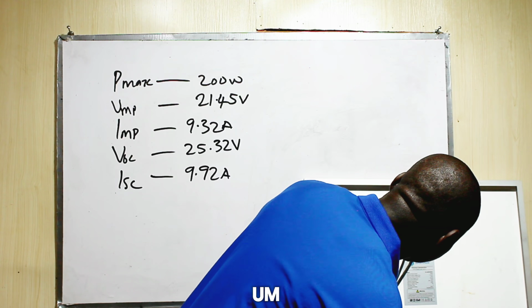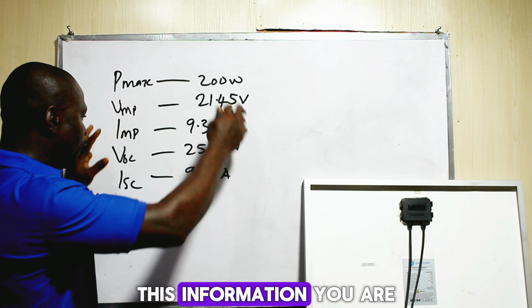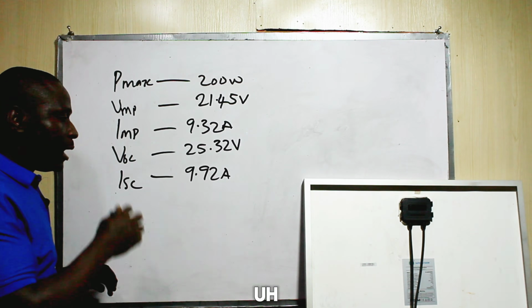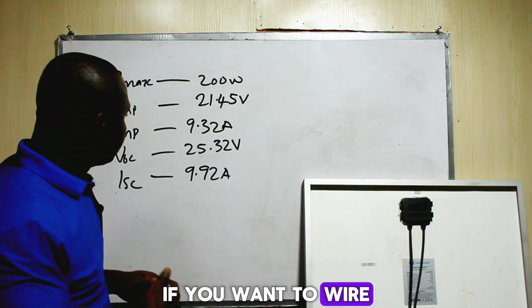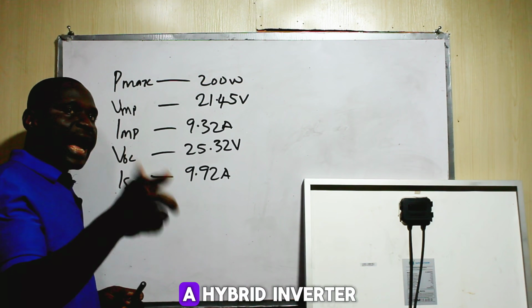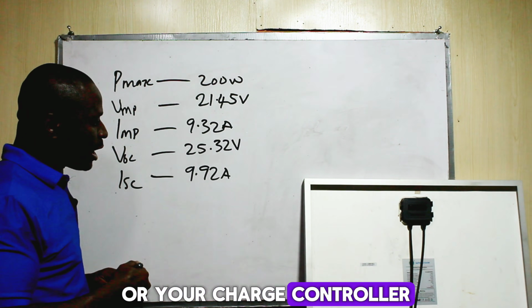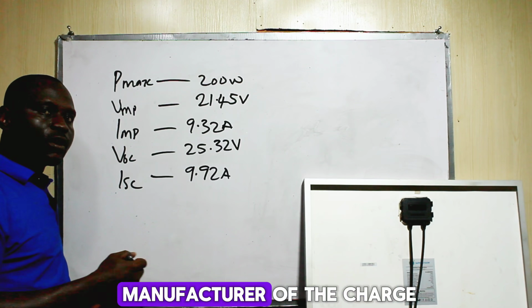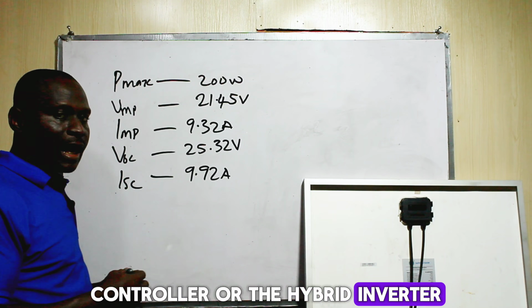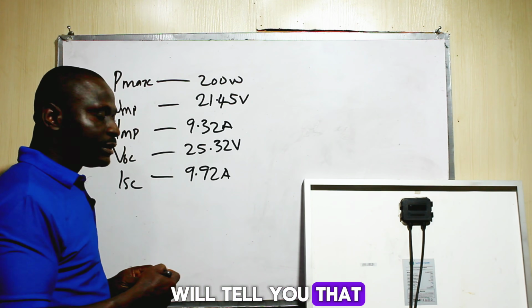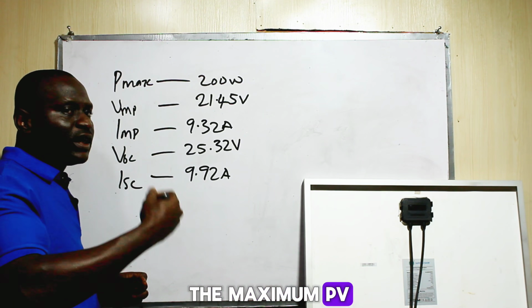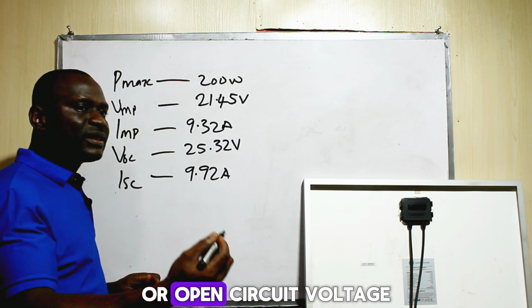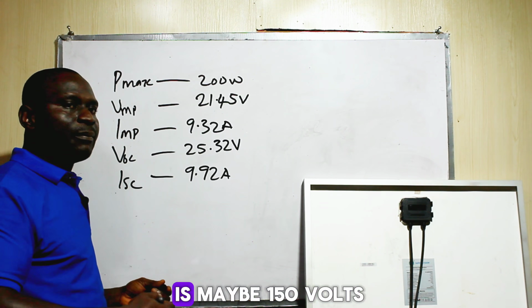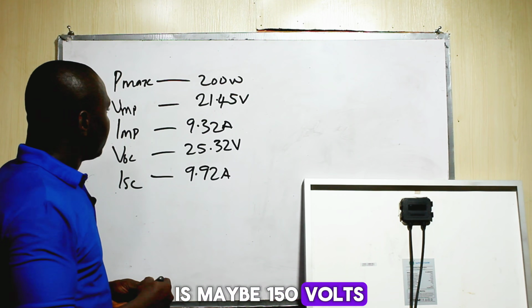This information is important if you want to wire this solar panel to a hybrid inverter or charge controller. You will see that the manufacturer of the charge controller or hybrid inverter will tell you that the maximum PV input voltage, or open circuit voltage, is maybe 150 volts.